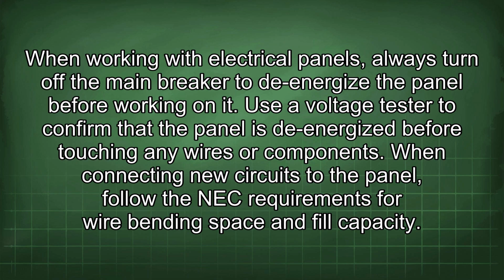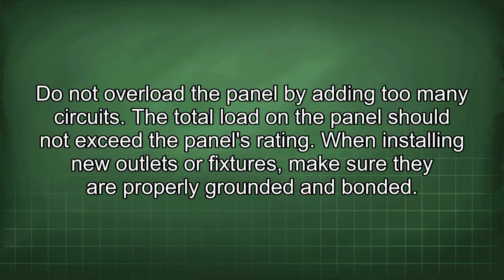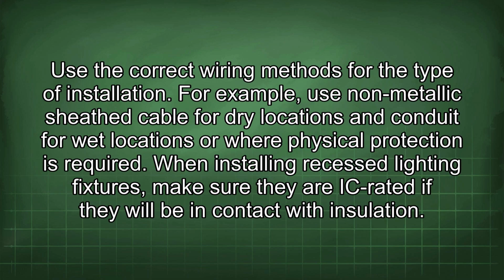When connecting new circuits to the panel, follow the NEC requirements for wire bending space and fill capacity. Do not overload the panel by adding too many circuits. The total load in the panel should not exceed the panel's rating. When installing new outlets or fixtures, make sure they are properly grounded and bonded. Use the correct wiring methods for the type of installation. For example, use non-metallic sheathed cable for dry locations and conduit for wet locations or where physical protection is required.